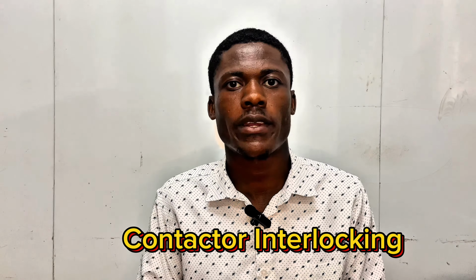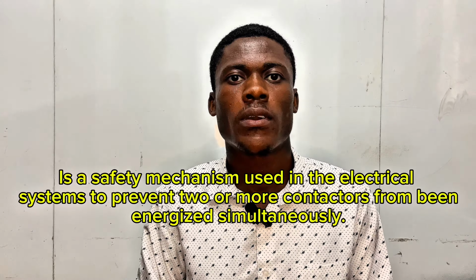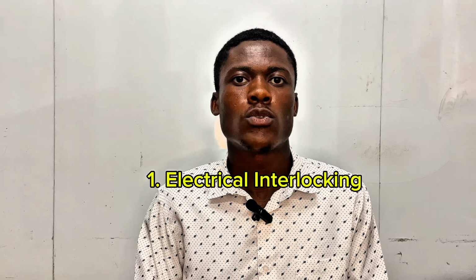And in this very video, I'm going to talk about contactor interlocking. And what is contactor interlocking? Contactor interlocking is a safety mechanism used in electrical systems to prevent two or more contactors from being energized. We don't want two or more contactors to be working at the same time. Hence, interlock is needed. Bear in mind that we have two main types of contactor interlocking. We have one as electrical interlocking and two as mechanical interlocking. And in this very video, we are going to be making good use of the electrical interlocking.